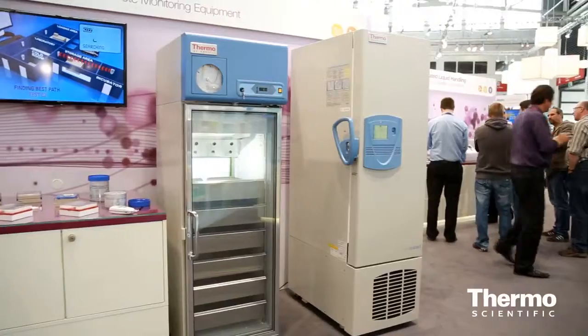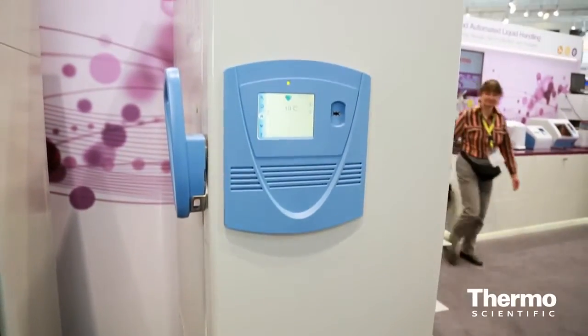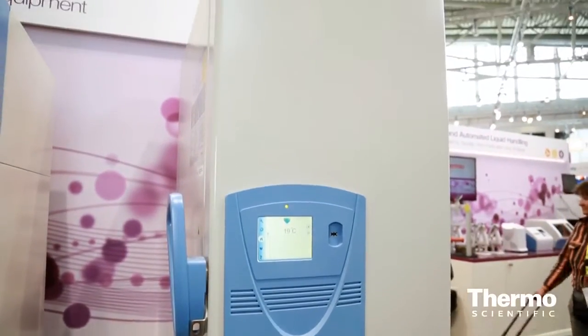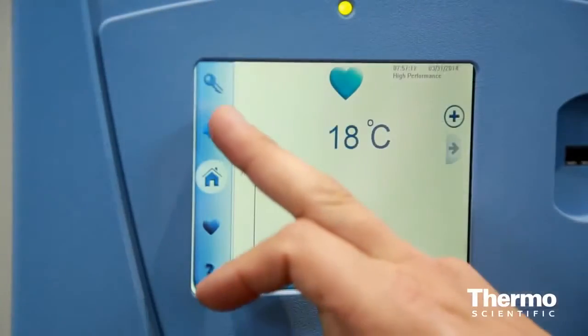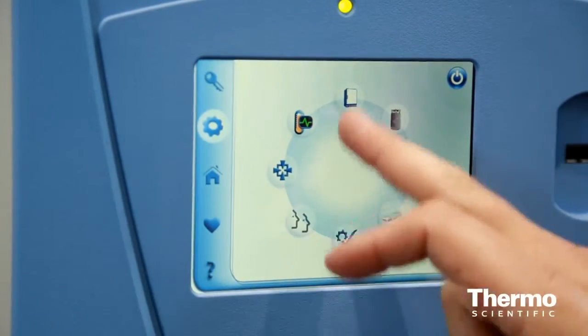Now we have that range within Thermo Scientific from +4 down to -196. And ultimately 80% of the samples stored are in the -86 freezers. If the samples are outside their parameters for any given time, obviously the sample integrity is affected, thereby the viability of those cells is gone.